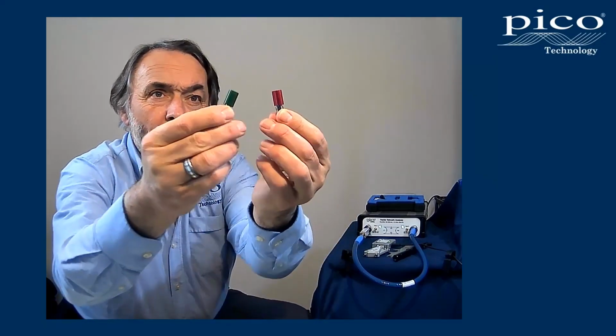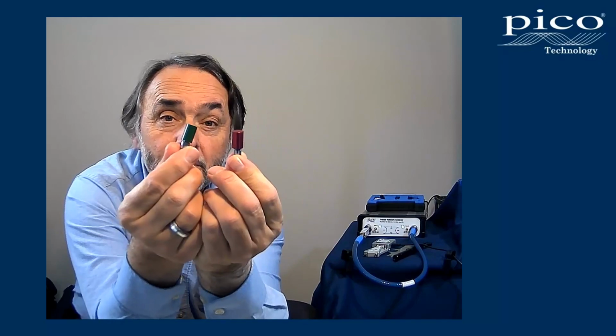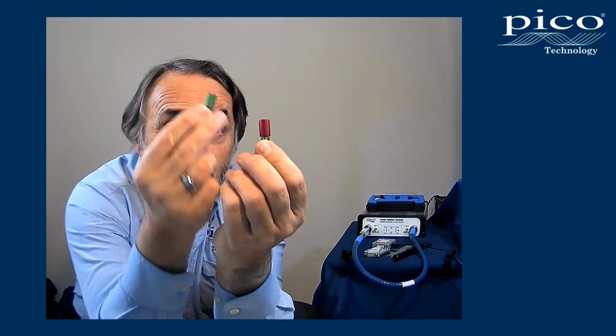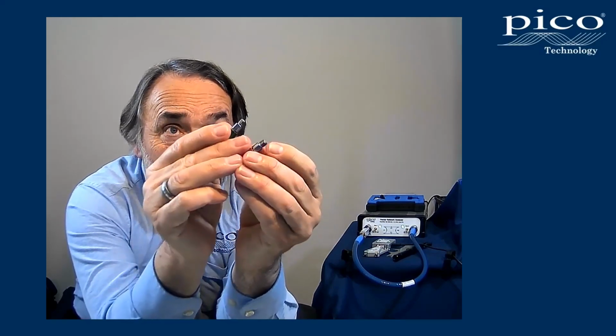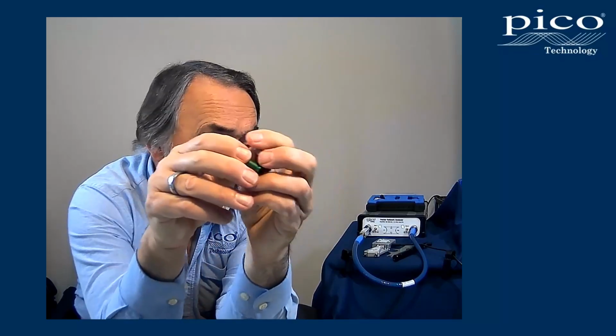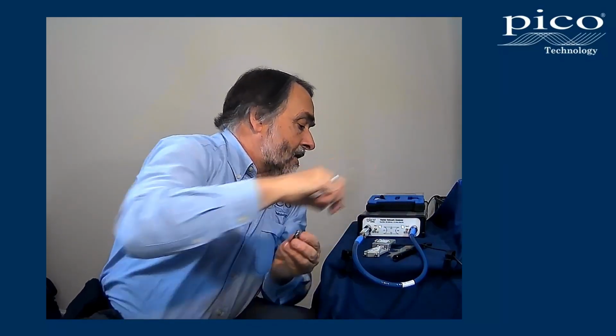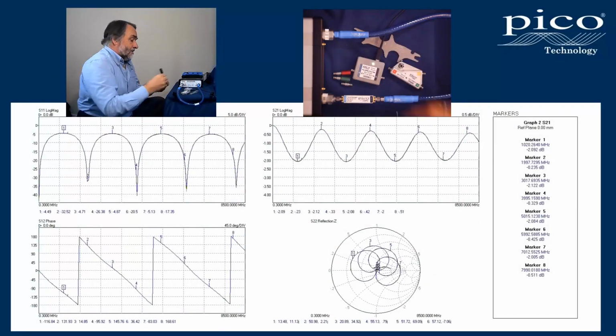So I'm going to do a comparison there as well, and I'm going to do that with another very well-known calibration kit. I mean well-known in terms of their traceability back to national standards. This is a very well-known open and a very well-known short, the red one, open the green one. I've got a very good through, and we'll now use these in our measurements to look a little bit further at the quality of the e-calibration relative to the manual calibration, and both relative to the specification of the instrument. Okay, so let's remove the check standard.